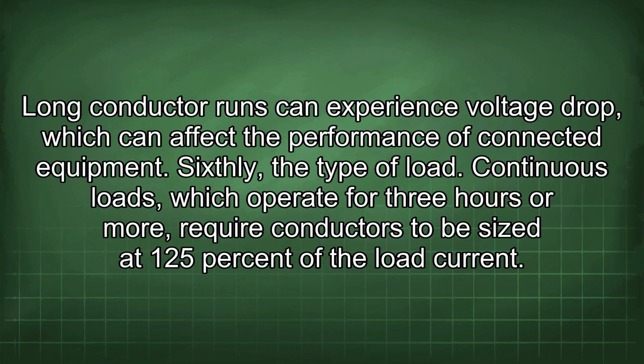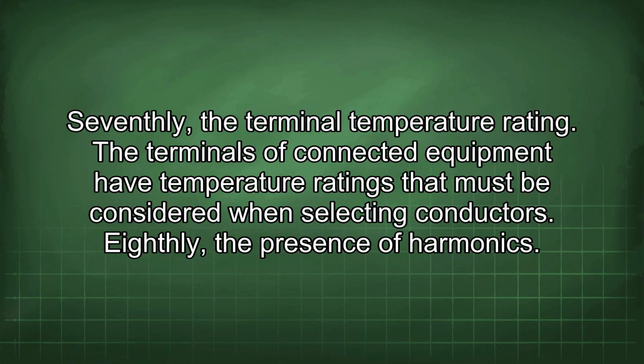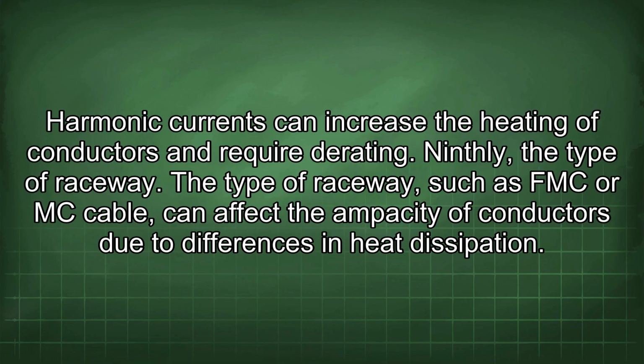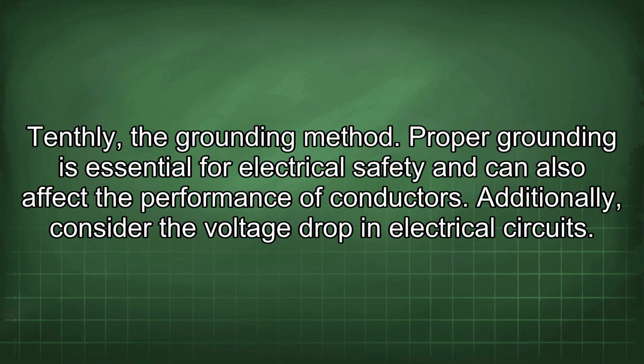Sixthly, the type of load. Continuous loads, which operate for 3 hours or more, require conductors to be sized at 125% of the load current. Seventhly, the terminal temperature rating. The terminals of connected equipment have temperature ratings that must be considered when selecting conductors. Eighthly, the presence of harmonics. Harmonic currents can increase the heating of conductors and require derating. Ninthly, the type of raceway. The type of raceway, such as FMC or MC cable, can affect the ampacity of conductors due to differences in heat dissipation. Tenthly, the grounding method. Proper grounding is essential for electrical safety and can also affect the performance of conductors.